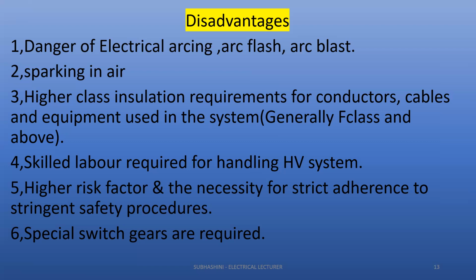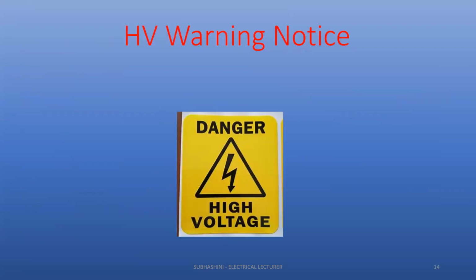Special switchgear is required. The switchgear we were using before cannot be used. We have to design it for our current rating. The variation of current is present, so according to that, and the switchgear short circuit current, we have to design the switchgear. This is the symbol of the HV warning notice. It can be placed in HV systems, wherever we can place it, as a danger symbol.